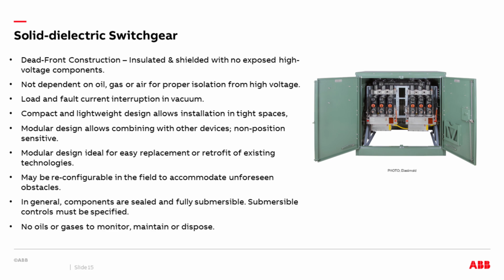So I'm showing a picture of solid-dielectric switchgear. Just a couple of points about switchgear. It's dead front, so it's fully shielded, and there's no live parts when you open the doors. Even though utility crews typically have specific safety operating practices that govern how they interact with equipment, whether it's live front or dead front, we don't drive that, but we do facilitate some ease of that because it's dead front.